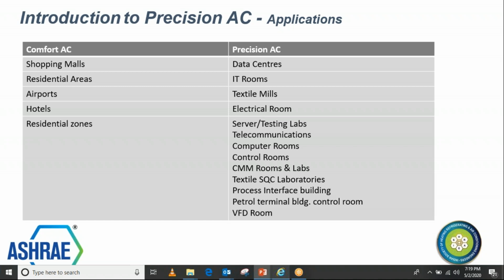And precision AC, which is more towards the right side of the screen, as you can see here, is all about electronics and electricals, and applications which run for 24 hours, and temperature and humidity which require precise control. So all the applications mentioned on the right side revolve around these 4-5 points, which come from the electronics and electricals present in that room. Temperature control: in some applications electronics may be less, but then temperature and humidity play a major role there, because it changes from application to application, and 24-hour operation. So this gives you an idea of how these two are different.